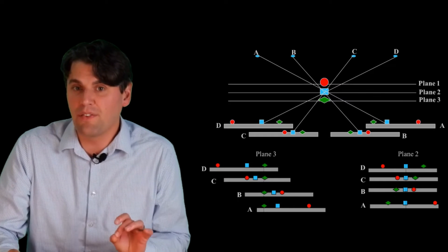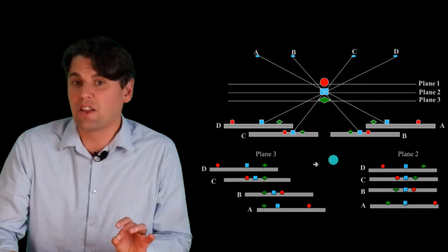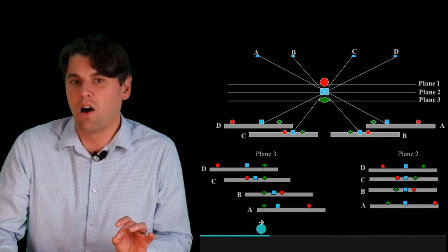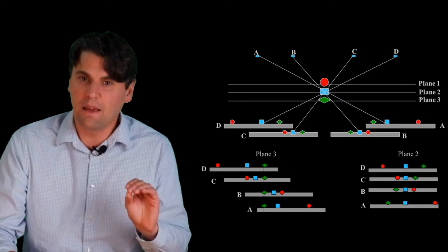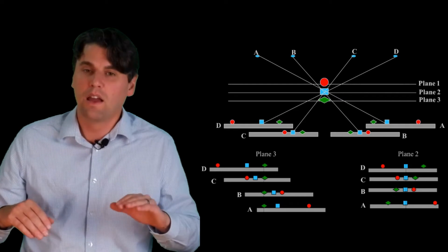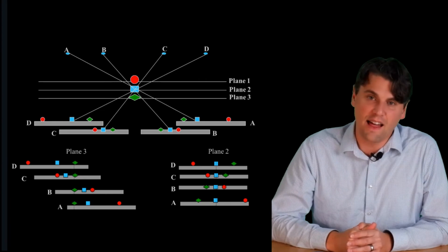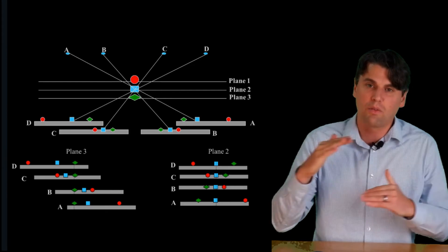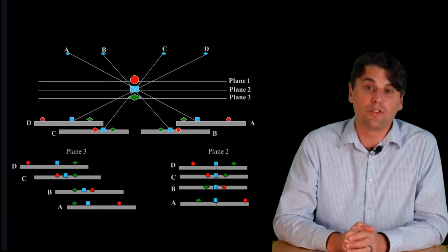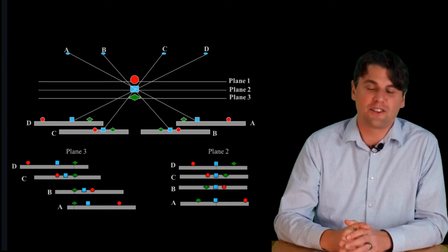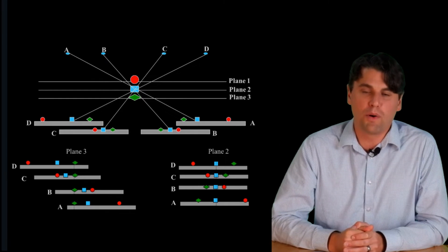So if you look at say our four acquisitions that we just call A, B, C, and D, and we can actually add these four acquisitions up in different ways. So if we just add them up without shifting them at all, what we get is the image where the thing inside of the focal plane is in focus, just like we talked about earlier. But if we actually shift them all with respect to one another, in this case, we could get the green diamond now to be all in focus. And that way we can make an image of plane three, where the objects above it are blurred out again, in this case in a line, because our source and detector were moving along that linear direction. This is what's called tomosynthesis, where you're actually synthesizing these image planes. And that's why it's called tomosynthesis.